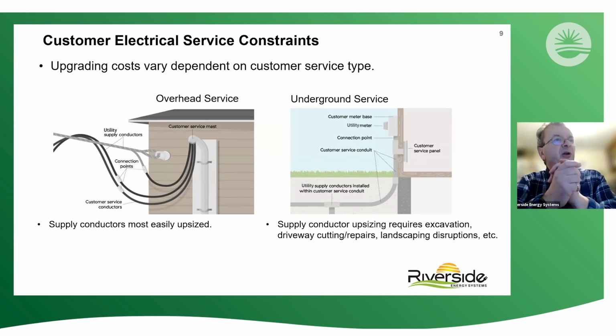Now, I want to be really clear. I'm not talking about upgrading the electrical panel to make it bigger. I'm talking about upgrading the service so that it can potentially draw more demand, more power from the grid when required. So let's not confuse upsizing a panel to create more breaker positions with upsizing the service. They're two very different things. I'm talking about upsizing the service.